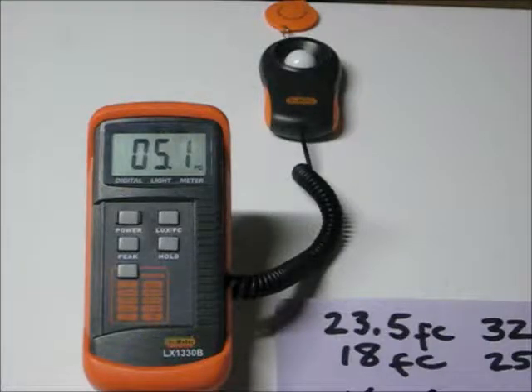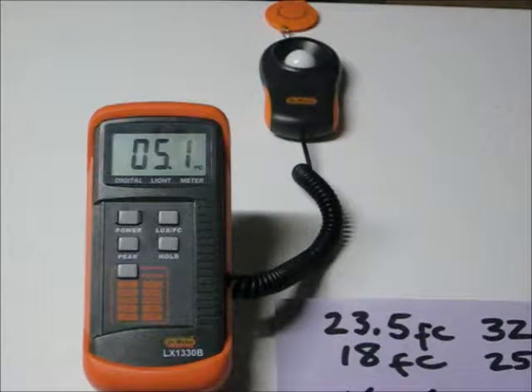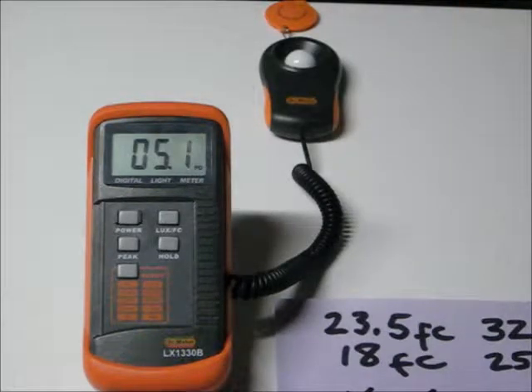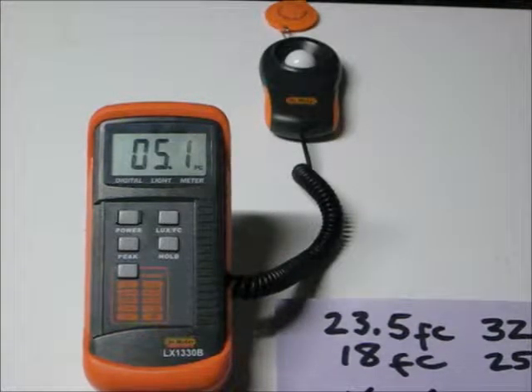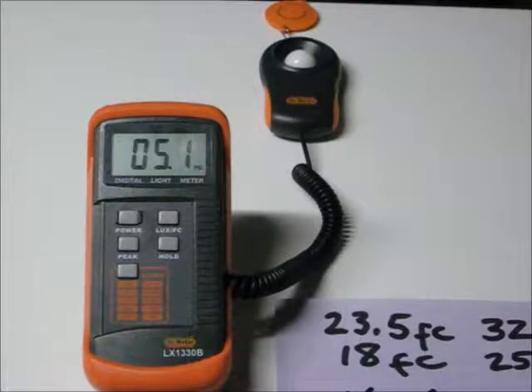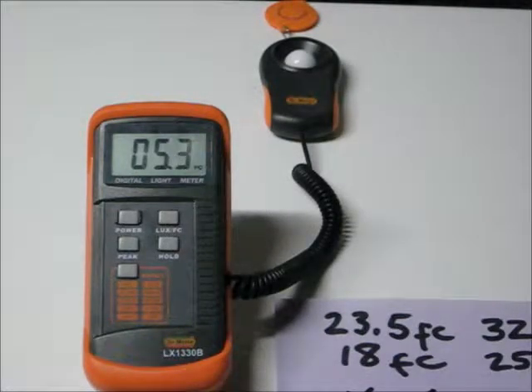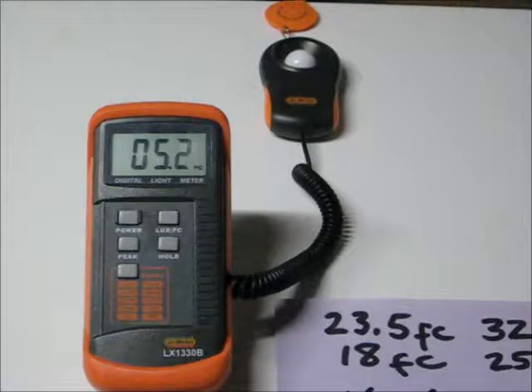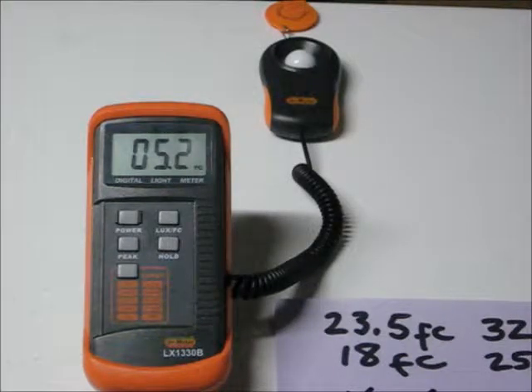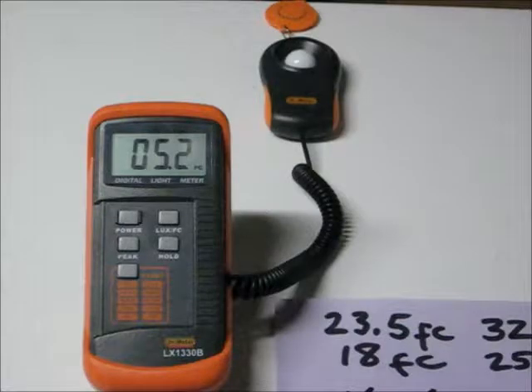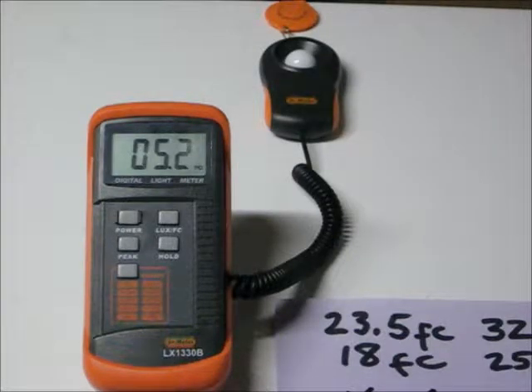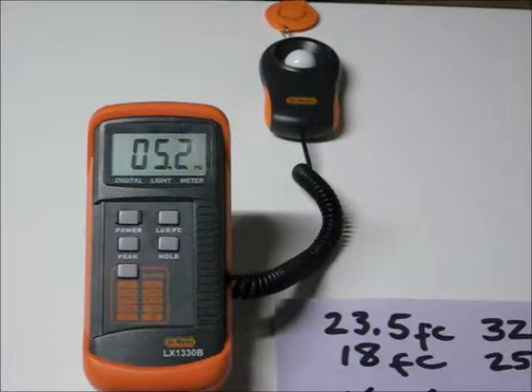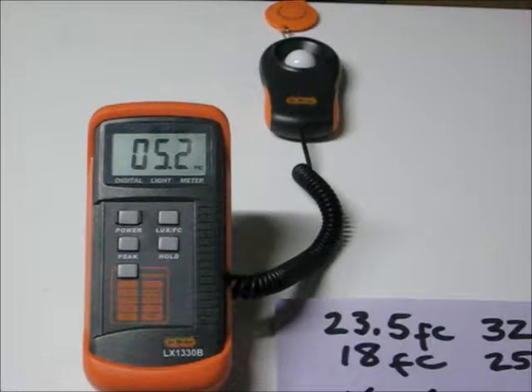Now, the 32-watt bulbs are 4-foot Philips F32s and F25s. The daylighting controller is an LS301, 0-10-volt, and we're using an Advance Mark 7 ballast. So what I'm going to do is set this thing for nighttime.